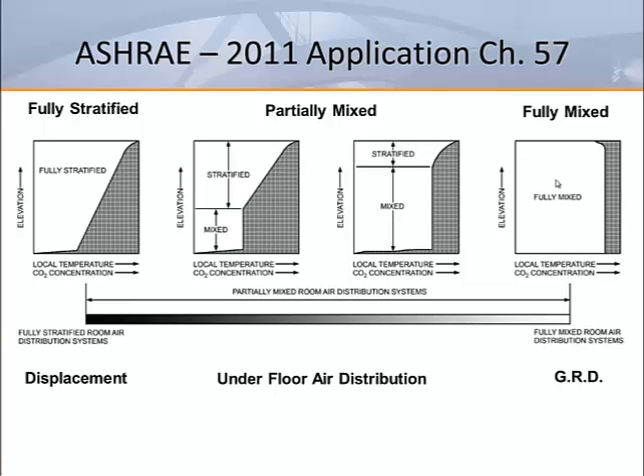For these spaces, it is typical for stratification to occur proportionally from just above the floor to the height of the return. The design goal for fully stratified systems includes controlling the stratification at a rate of about 1 degree Fahrenheit per foot of rise. This will meet the temperature stratification requirements found in ASHRAE Standard 55.